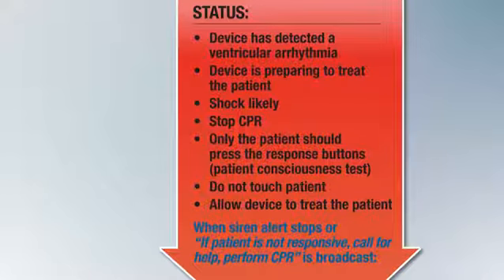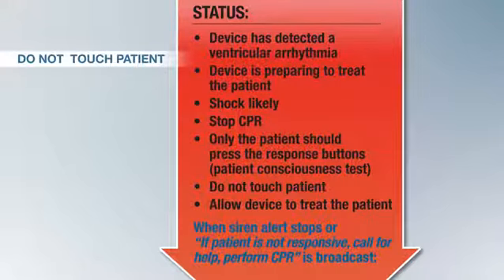Please note that you can be shocked if you are touching the patient when the shock is delivered. Do not touch the patient when the LifeVest is in this mode. Allow the LifeVest to complete the treatment sequence and shock the patient. The device will broadcast when it has completed the treatment sequence. The sirens will stop and you will hear the following instructions. "Treatment has been given. Call your doctor."